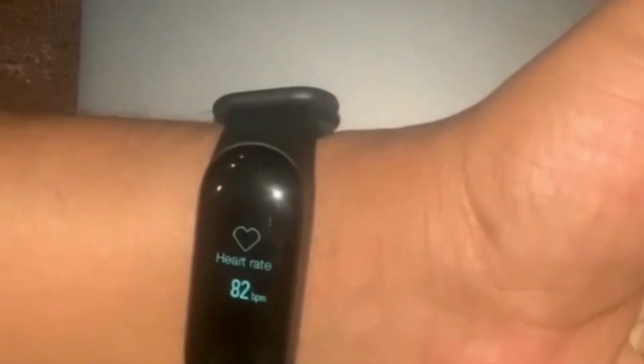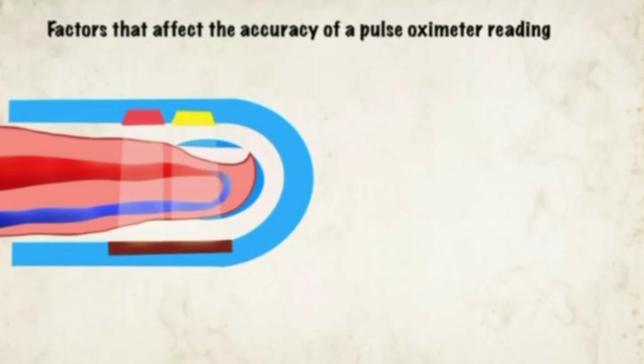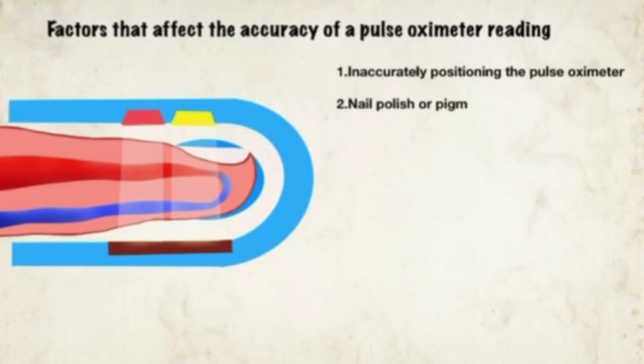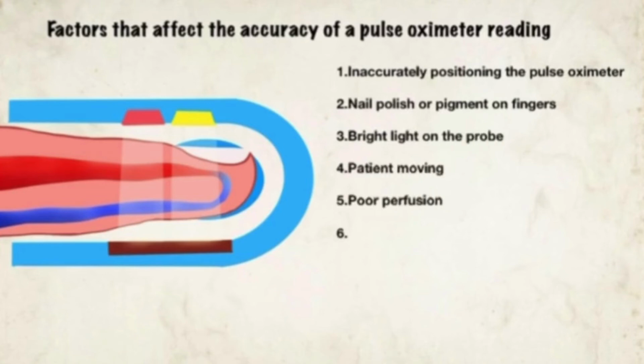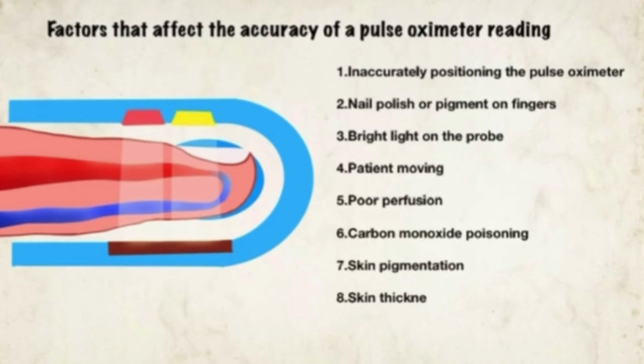Checking the accuracy with a smartwatch, we have obtained 95% accuracy. Factors that affect the accuracy of pulse oximeter readings: inaccurate positioning of the pulse oximeter, nail polish or pigment on fingers, bright light on the probe. Other factors are patient movement, poor perfusion, carbon monoxide poisoning, skin pigmentation, skin thickness, current, and tobacco use. These are the factors which affect the accuracy of pulse oximeter readings.